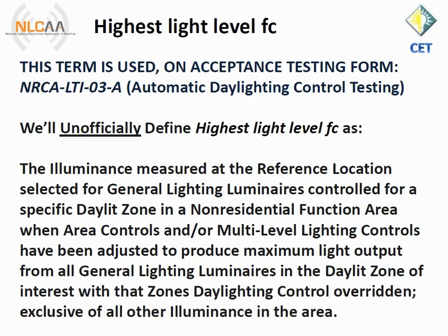The acceptance test technician will be required to estimate or measure power reduction in a daylit zone. This is not taken from design or reference illumination, but in fact taken from full output, or highest level foot candles, is what the form entry says.